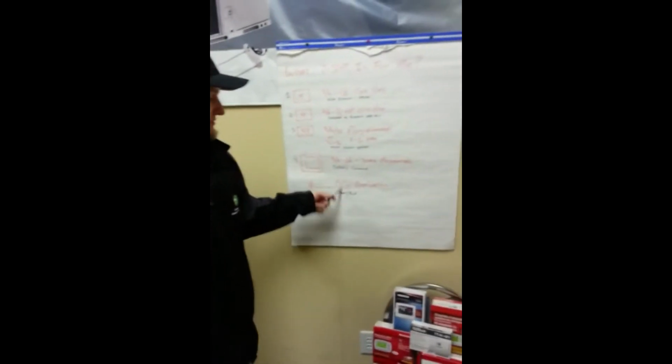If you have the wrong setting, you're going to be running cool in the wintertime and hot in the summertime. And obviously it's not going to work. The main brand that we know of, the primary one in their market, is Rheem and Ruud, which is the same company. They typically use B for their reversing valve.